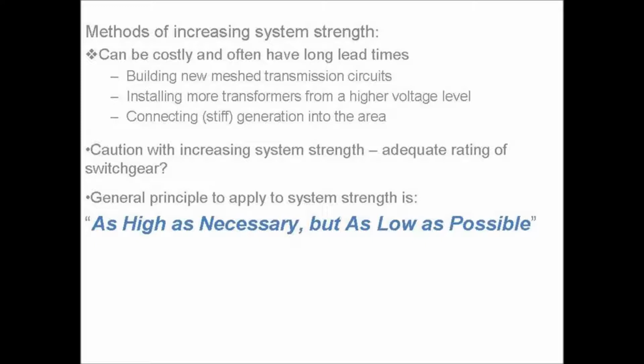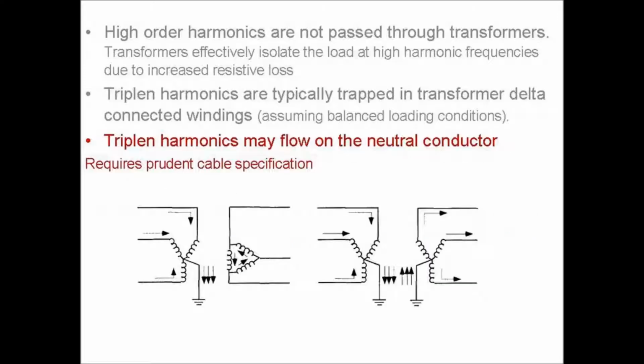Then I suppose the other thing is, safety is the big concern on the grid, and you need to make sure that your switchgear is rated to handle these higher short circuit currents. So you want it to be high enough that it's able to push the harmonics out of the range, but you want to keep it as low as possible, because you want your switchgear to work when it needs to, so your circuit breaker will open whenever there's a fault.